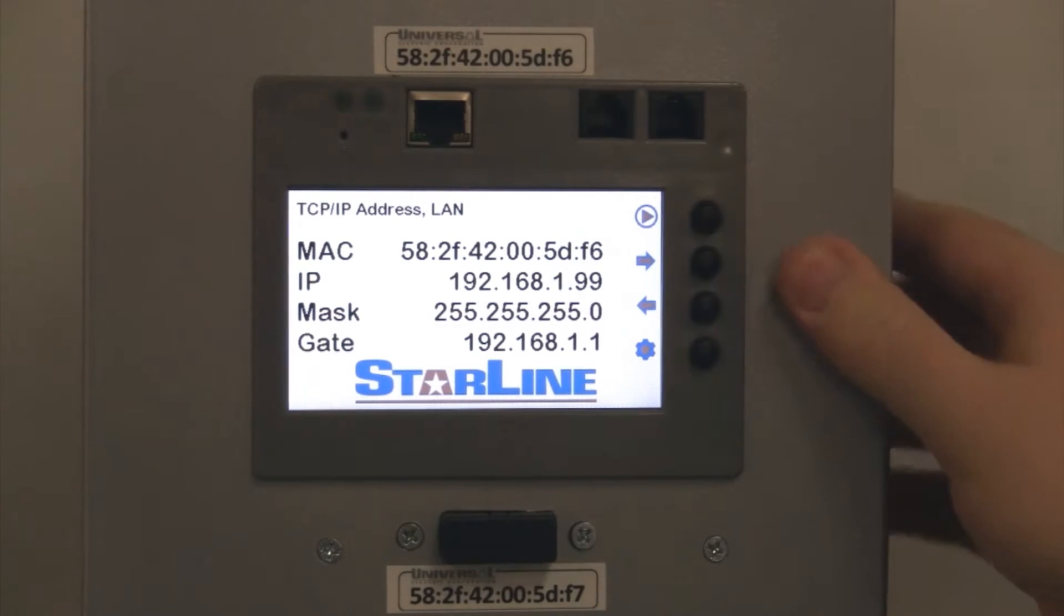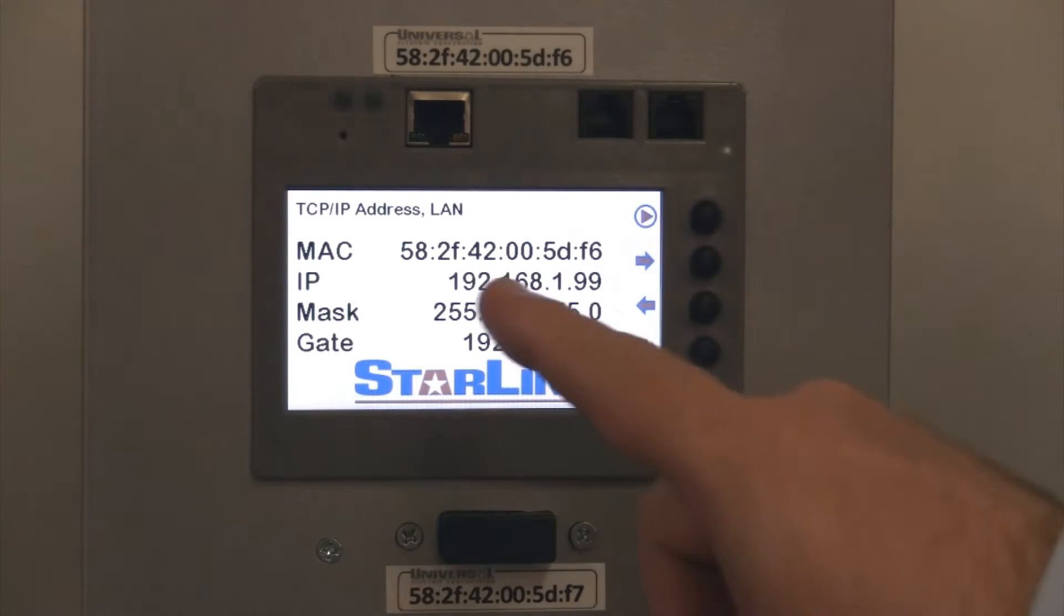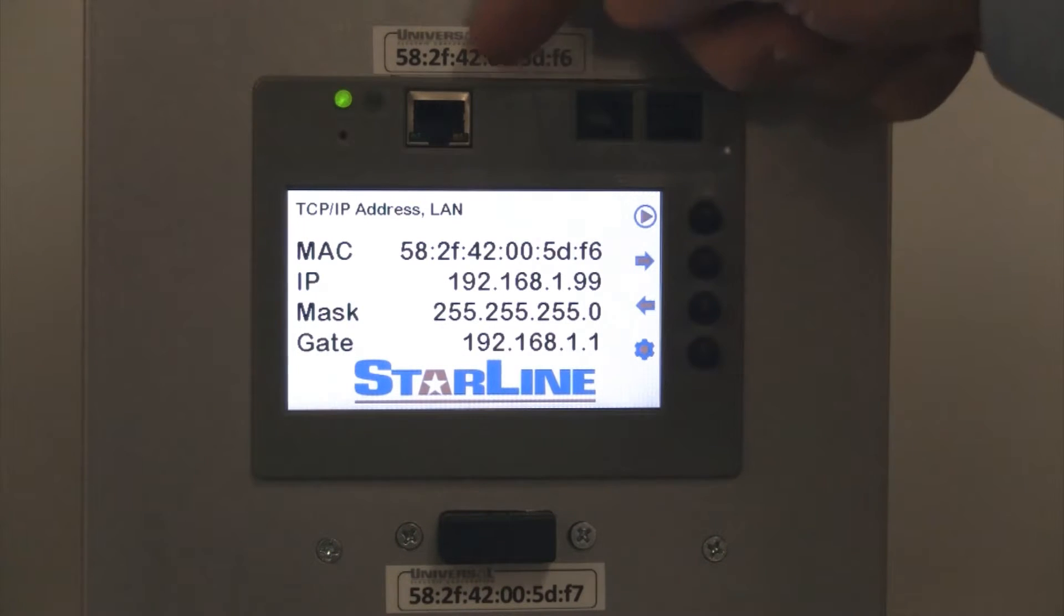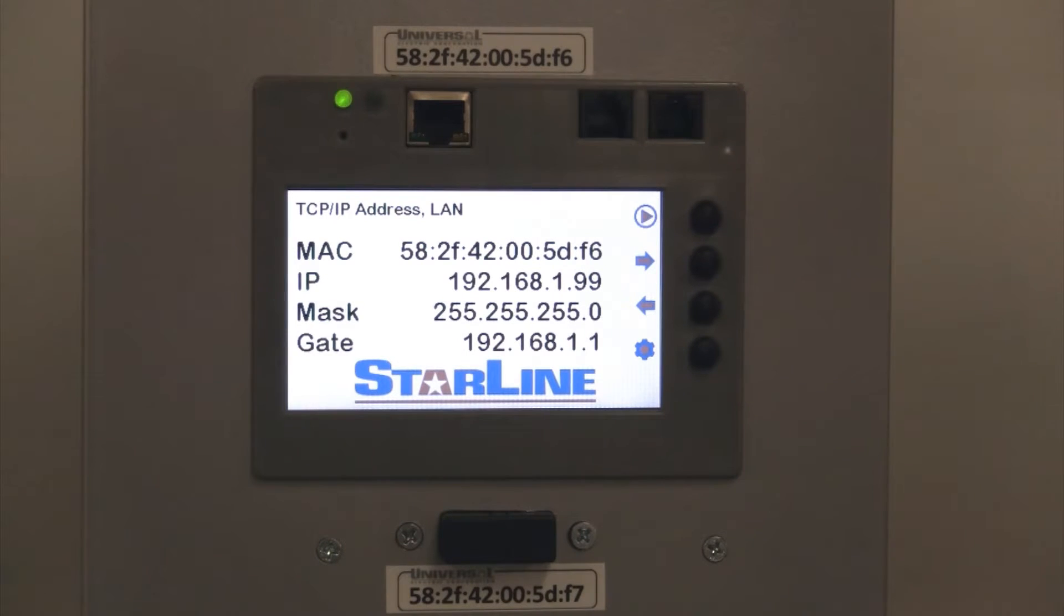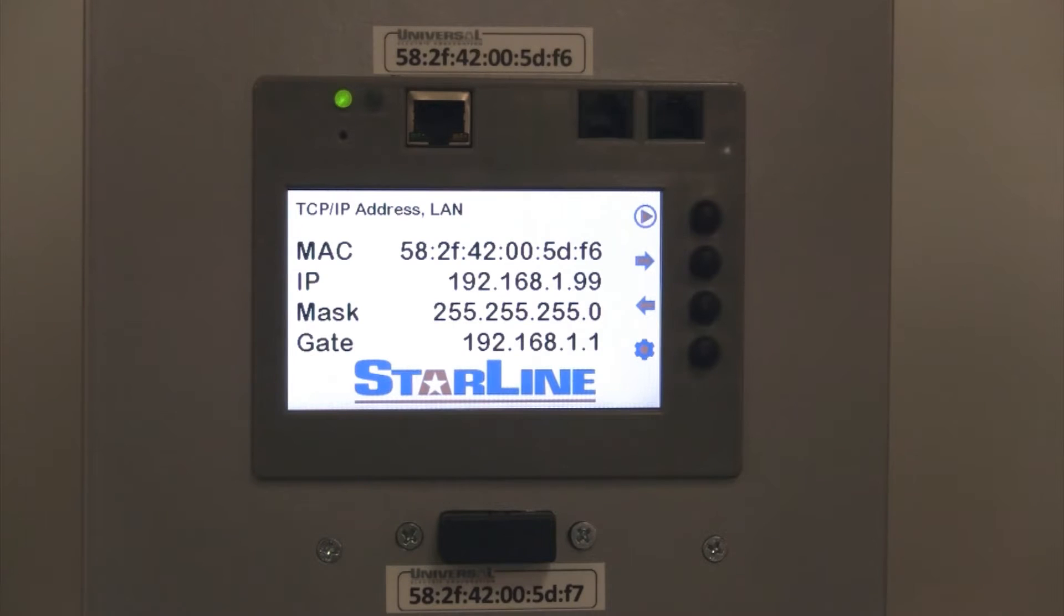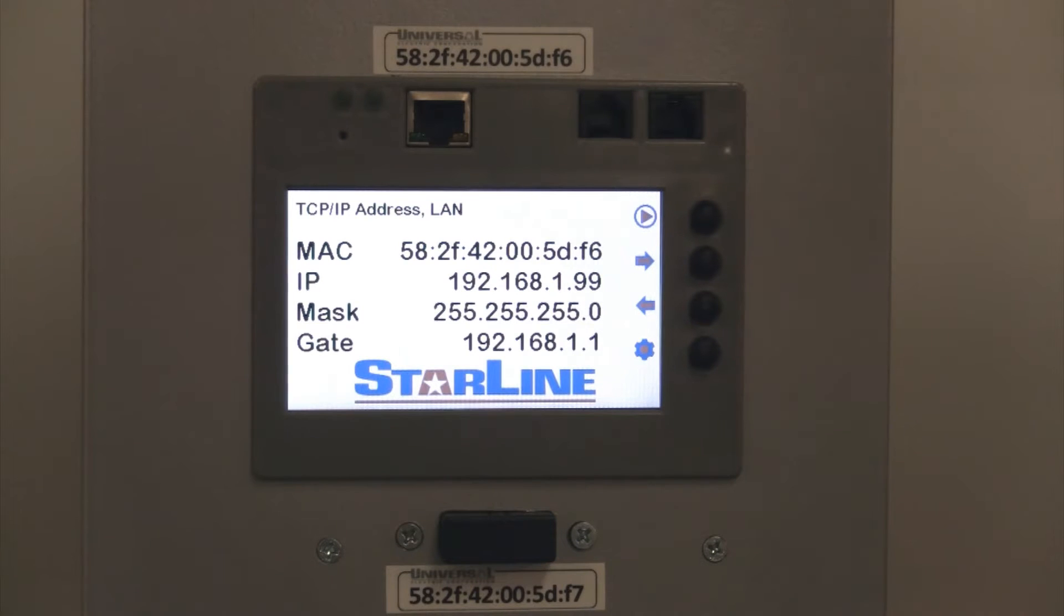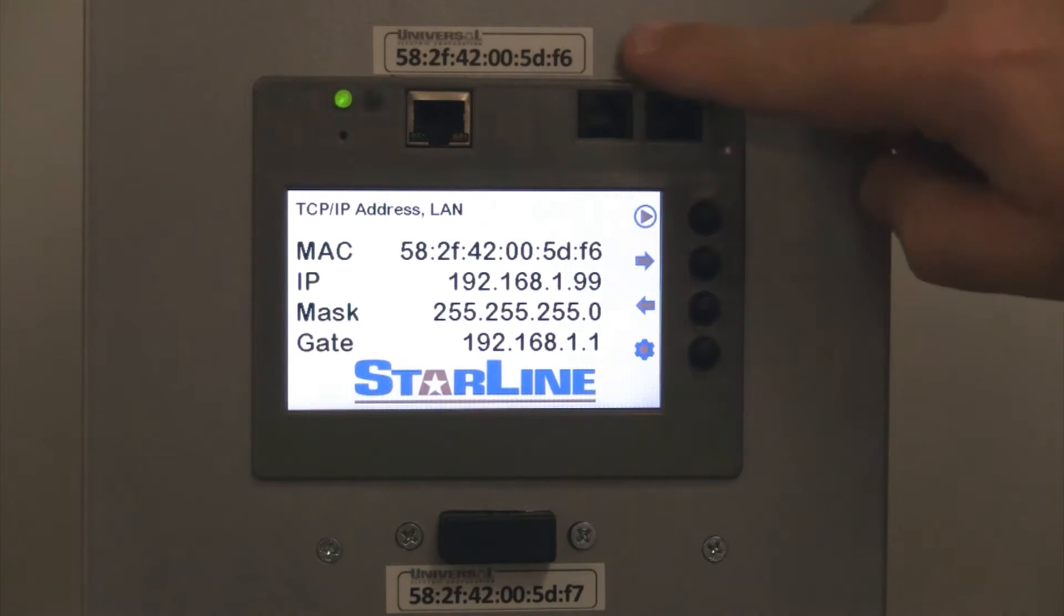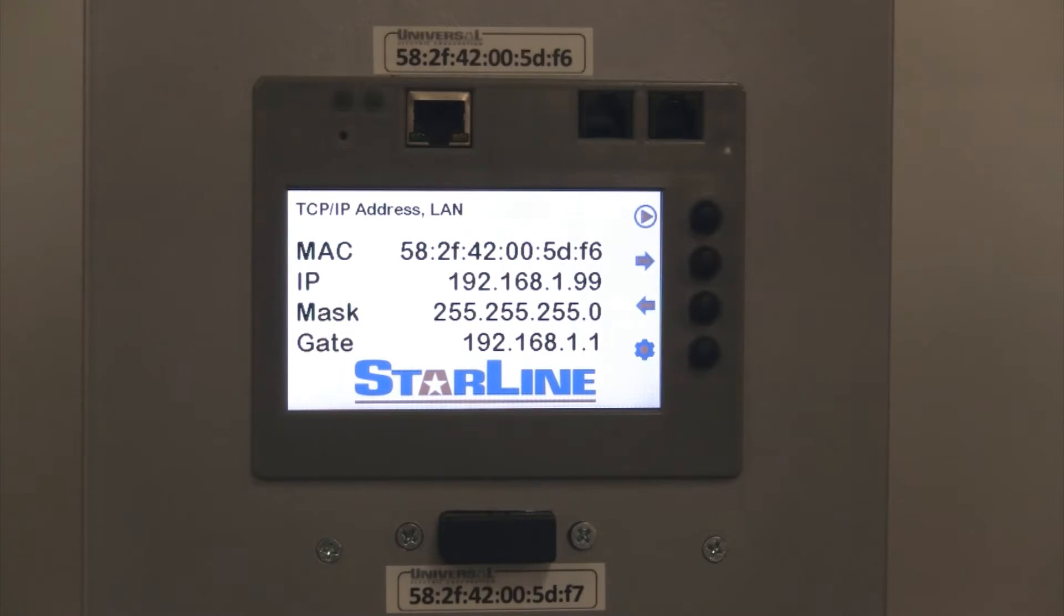The screen that's up now actually shows the IP address information. So you can see that's the LAN side, the Ethernet port on the front here. By default, the IP address is set up to 192.168.1.99. That is how the unit will come configured from the factory. So whenever you want to log in to the integral webpage to make changes to the IP addresses, set alarms, any information that you can configure, that is the IP address you'll need to know. You can see the MAC address, which is on the sticker above, also displayed on the unit on the screen.